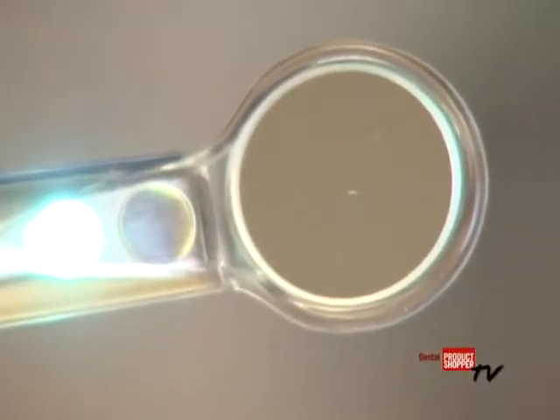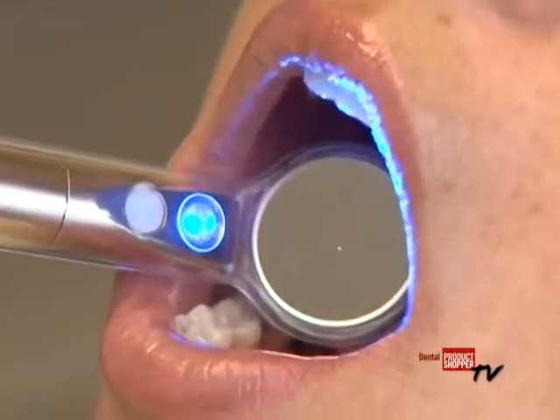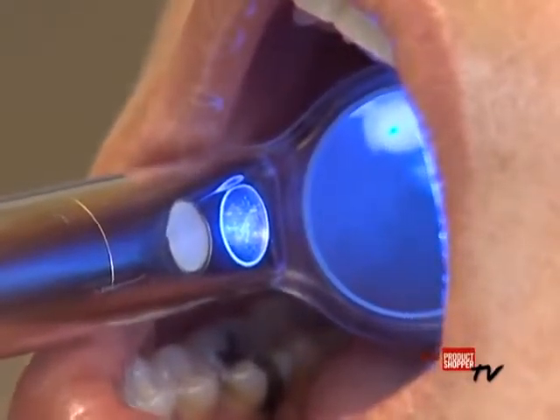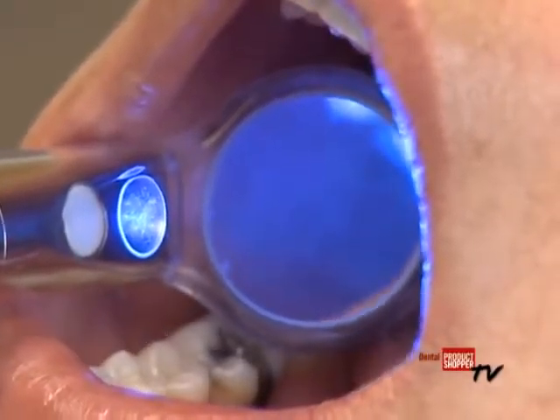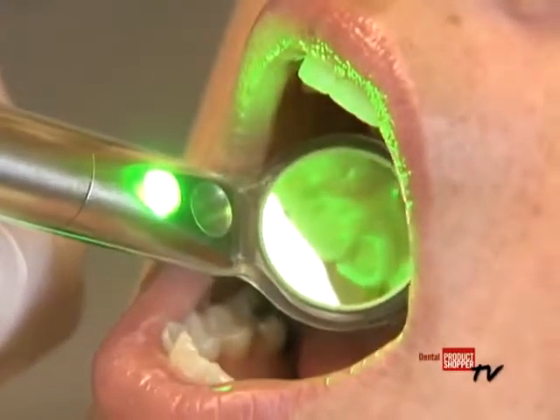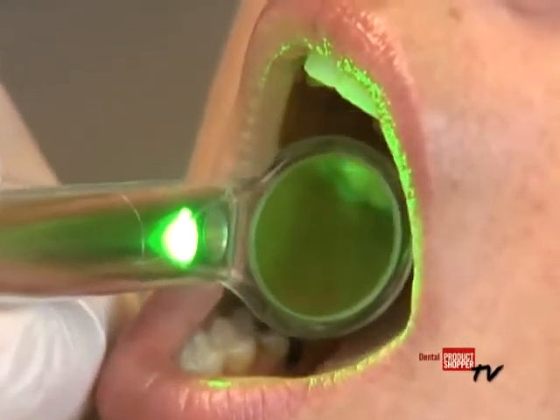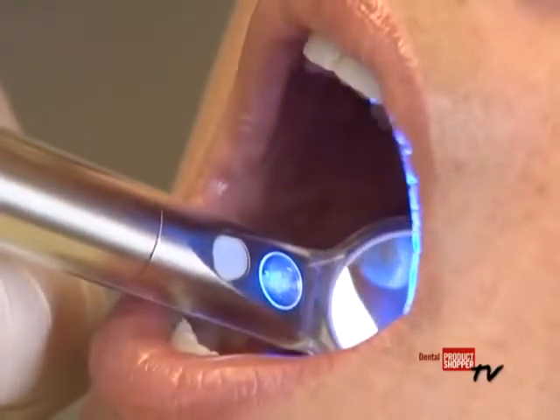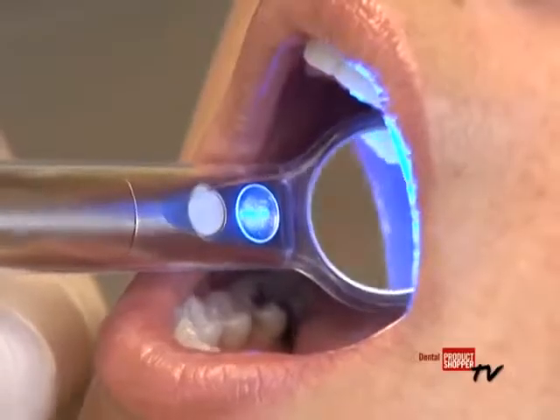The highly concentrated white light is used during the conventional exam. The patented 405 nanometer violet light enhances the fluorescence of normal tissue, but suspicious tissue will appear dark. The green amber light helps the user see the difference in the blood vessels between the normal and abnormal tissue. Research shows that tissue with diffuse vascularization is more likely to become cancerous.